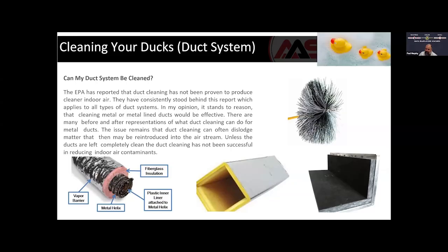If you really need to have the ducts cleaned, I mean, most of the time, and we do a lot of work for Chase Bank, we suggest just replacement. If the ductwork is that compromised, we just go ahead and replace the ductwork rather than trying to clean it. The EPA has done a report that duct cleaning has not proven to provide a cleaner indoor air, and they have consistently stood behind that report.